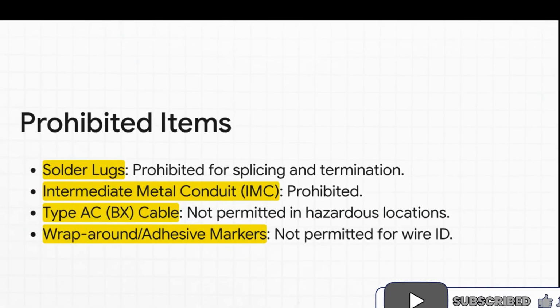Knowing what to do is important, but knowing what not to do is just as critical. The standard is very clear on things you just can't use. Solder lugs for terminations? Nope, prohibited. Intermediate metal conduit or IMC? Not allowed. Using those little wraparound sticky labels for your wires? Not permitted. It's these details that really show you know your stuff.